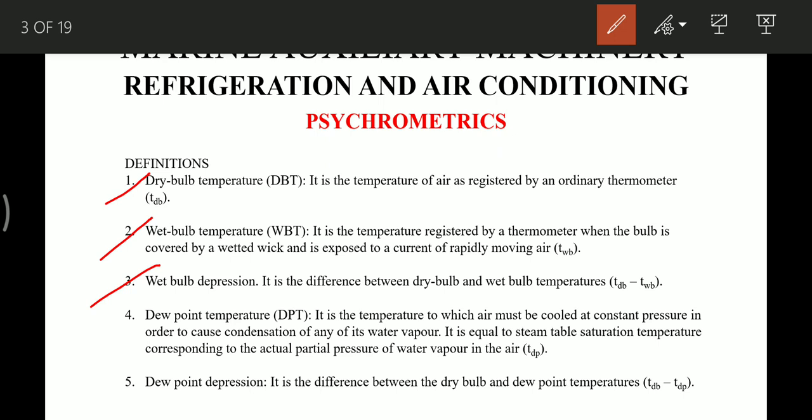The fourth definition is dew point temperature: it is the temperature to which air must be cooled at constant pressure in order to cause condensation of any of its water vapor. At the dew point, any water vapor present will condense to water. It is equal to the steam table saturation temperature corresponding to the actual partial pressure of the water vapor in the air. The fifth definition is dew point depression: it is the difference between the dry bulb temperature and the dew point temperature.